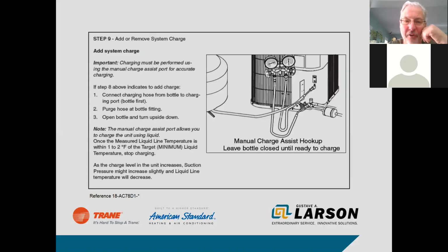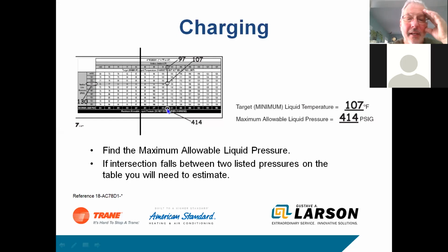When you look at microchannel, there's a charging chart, and it's like an approach temperature. So if you put your gauges on there and you see these numbers, 97, 107 is where you should be, and your high side is 414. If your pressures are below this, you need to add refrigerant. If your pressures are above this, you need to remove refrigerant. I'm not going to spend a lot of time on it, but there is a chart specific to each, and the 2-ton and the 3-ton are different. So if you run into microchannel, make sure you don't charge it by subcool or superheat. It's a whole different animal. It's got to be done totally differently.